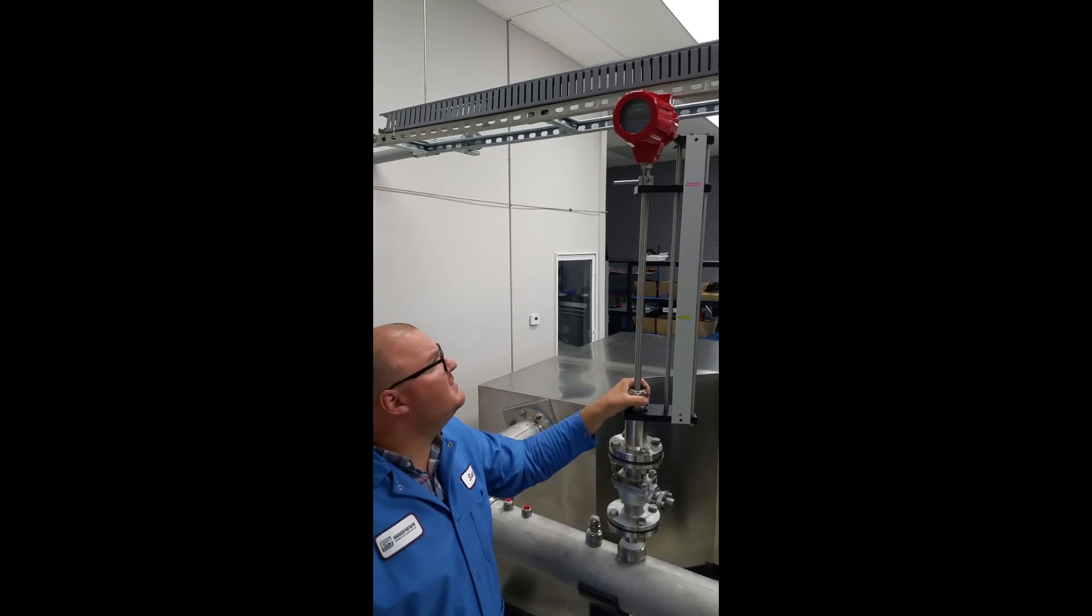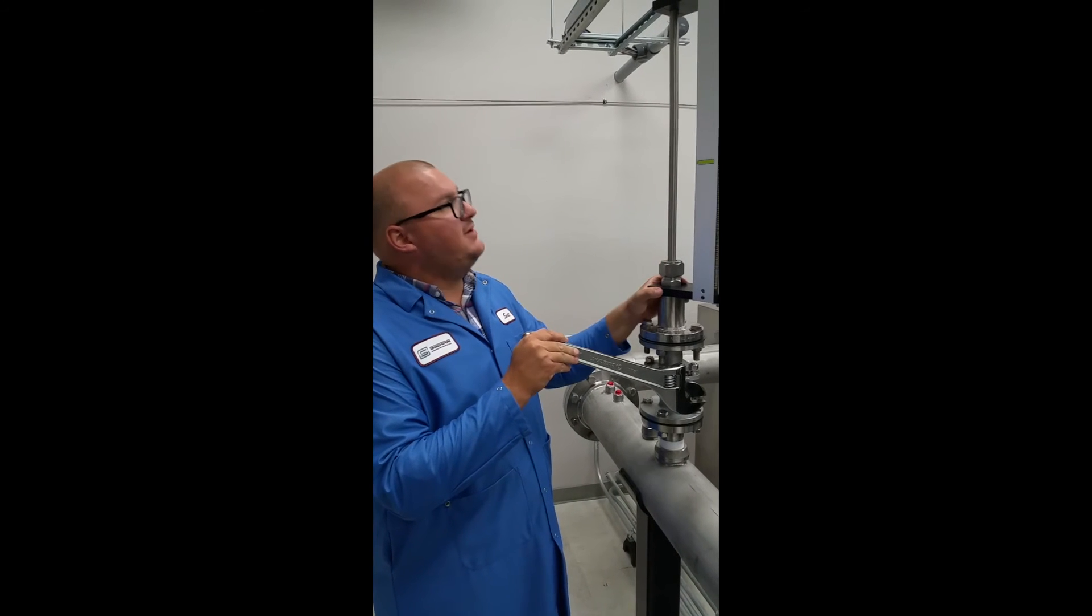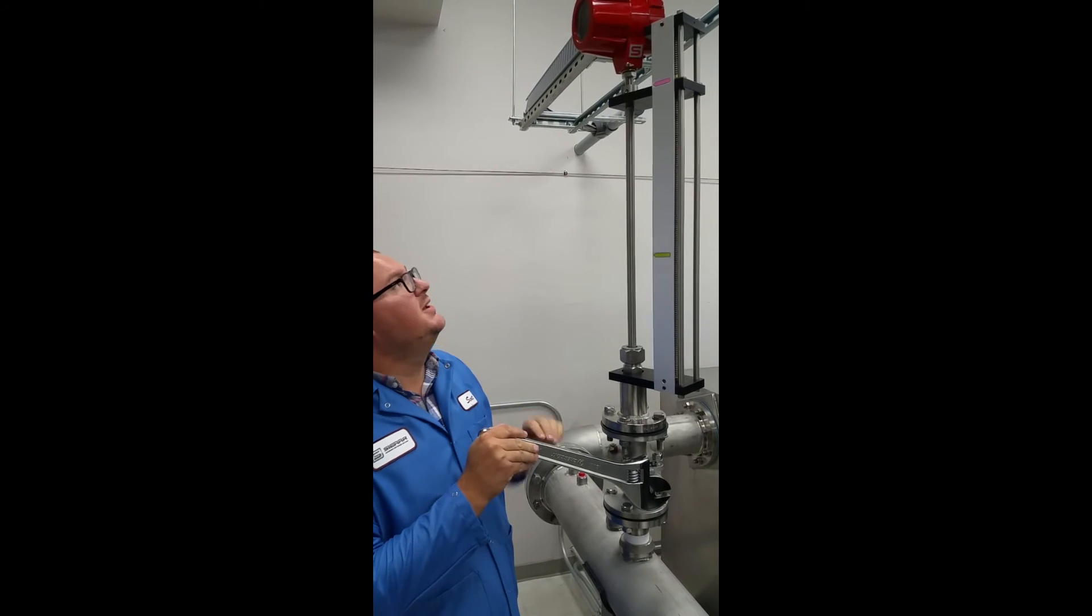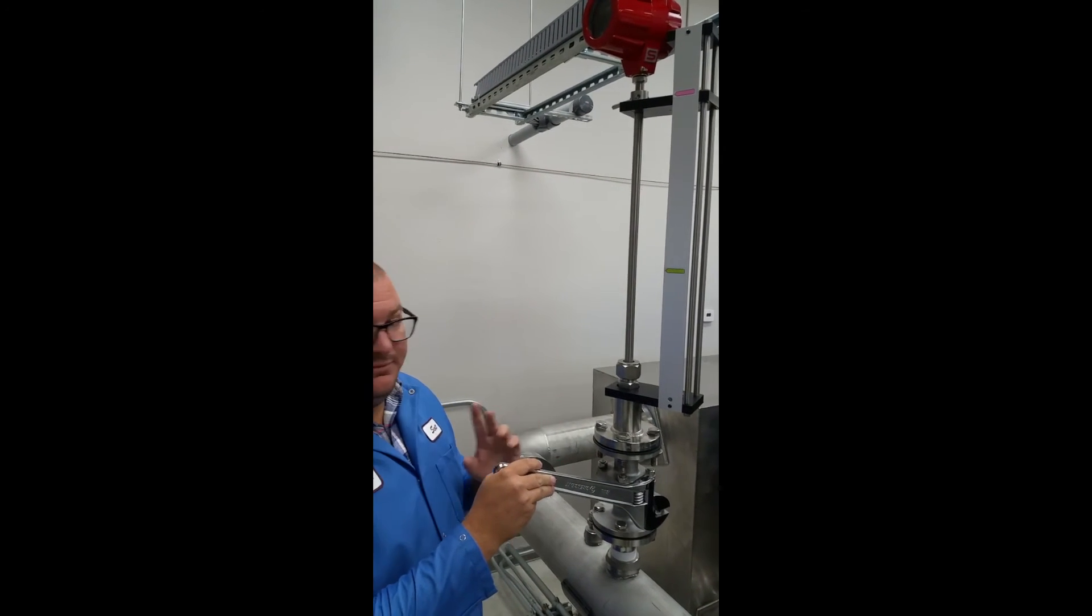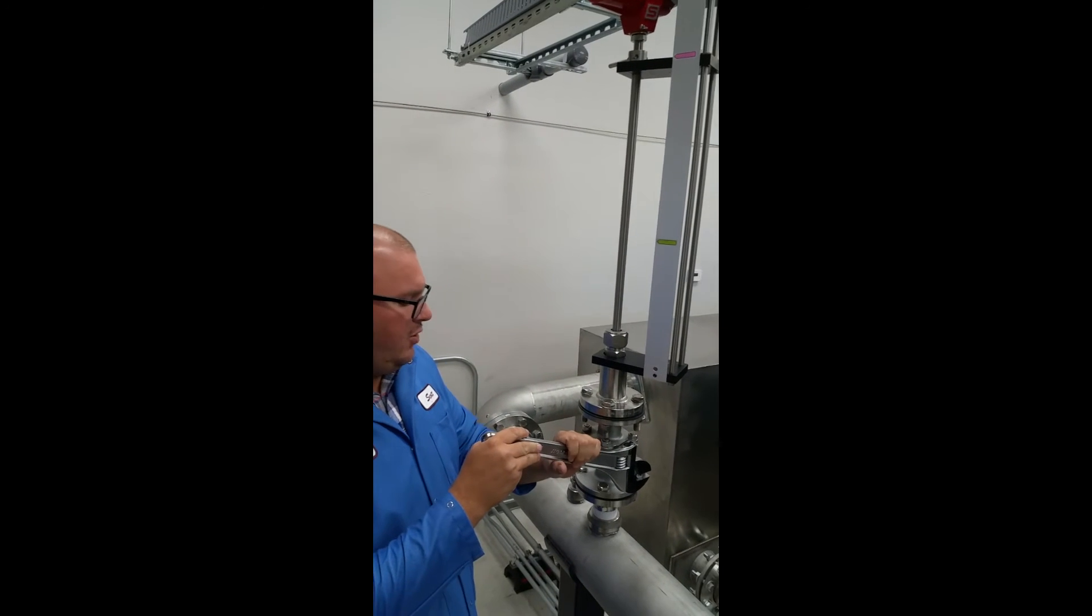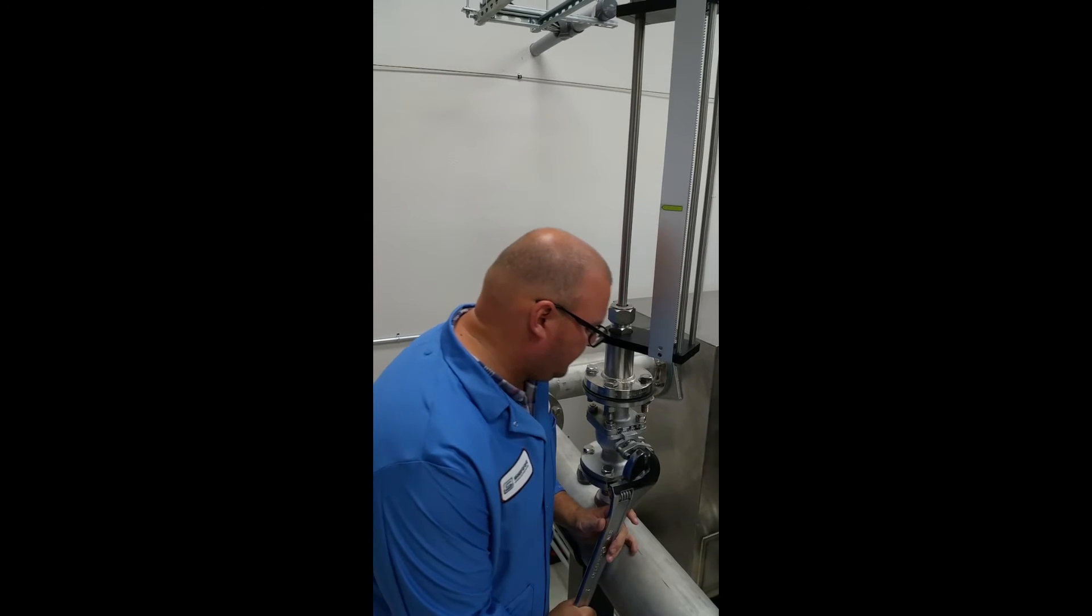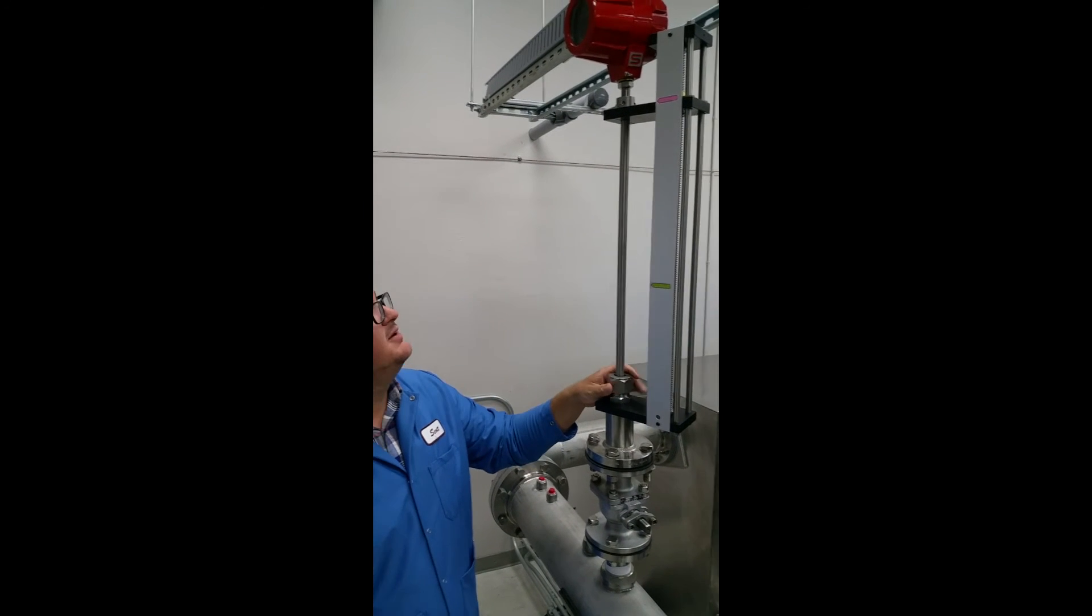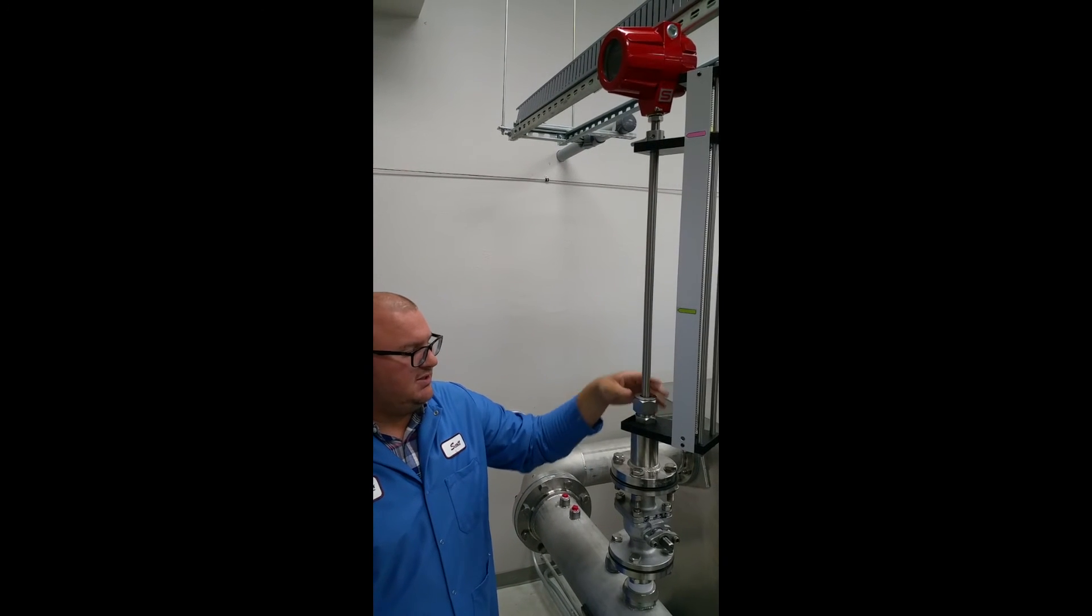My isolation valve is closed. Right now, this packing gland is tightened. It's hand tightened. Now my retractor is secured. I've checked my flow pointer to make sure it's in the right direction. I'm ready to insert this probe into the pipe. First step is going to be to open my isolation valve. Open this up. Next, I'm going to loosen the nut on the packing gland here to ensure that the probe can move easily up and down. You want to do this slowly.